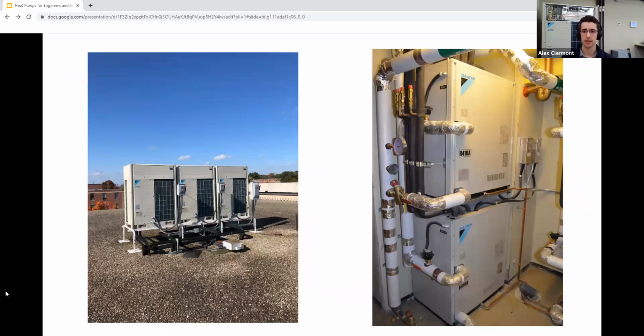What we're looking at here on this slide are two different types of VRF system. On the left, you have an air source VRF system, which uses the air to absorb and reject heat, while on the right, you have a water source VRF system. On the left, you see the air source machines on stands on the roof, and you see that black piping below it. Those are the refrigerant piping going into the building, going to the branch boxes and all the indoor units. So water source VRF will have the same refrigerant piping going to branch boxes and indoor units, but the only difference is the machines doing the heat transfer. In the air source case, they're outside, but in the water source case, they're indoors in a mechanical space. As you can see, the white piping on the right is the water piping from the rest of the building. But the black piping again is the same refrigerant piping.